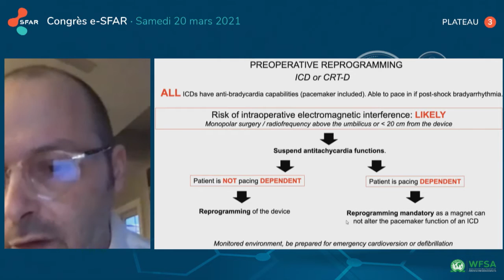About the magnet, its application is supposed to alter the pacing function to asynchronous mode only for a pacemaker, not for an ICD, very important, and to suspend the tachycardia function for ICDs. Some of them, like the Medtronic and Boston Scientific, can also emit an audible tone, proving that the ICD is actually deactivated. So magnets should be limited to rescue indications.